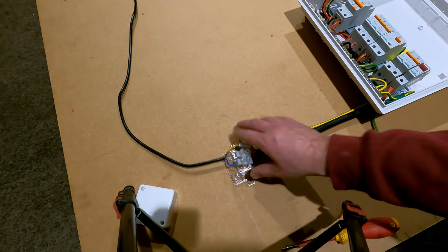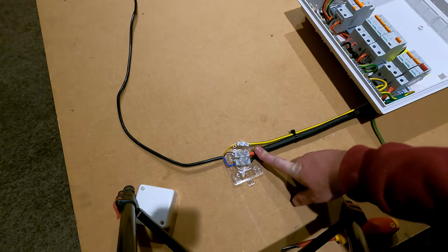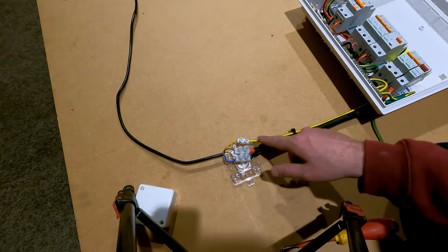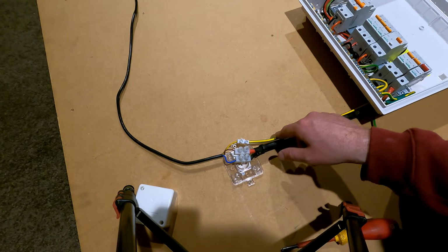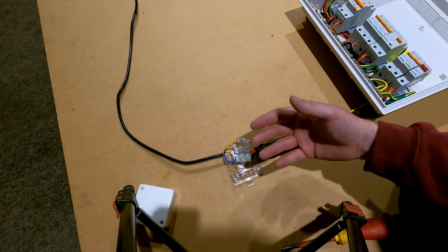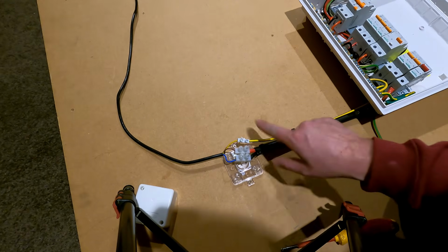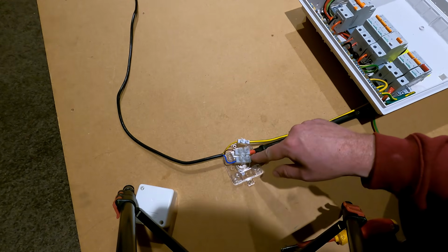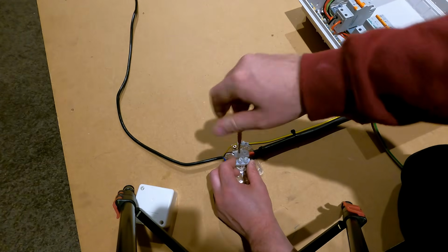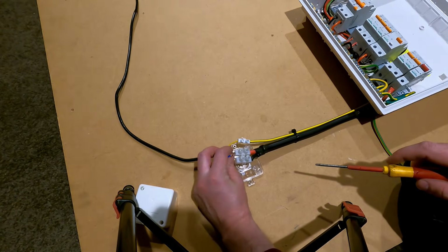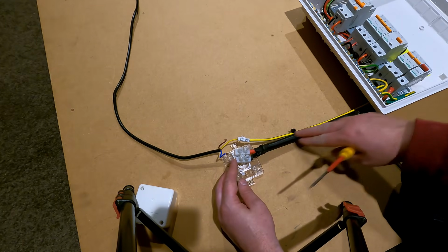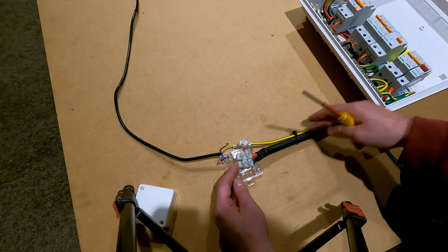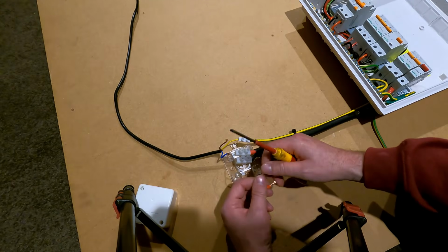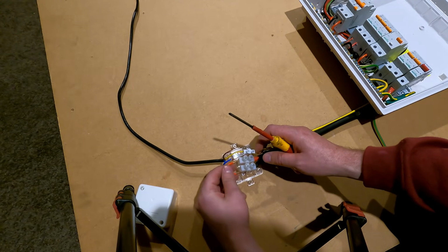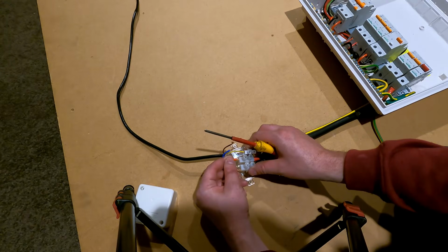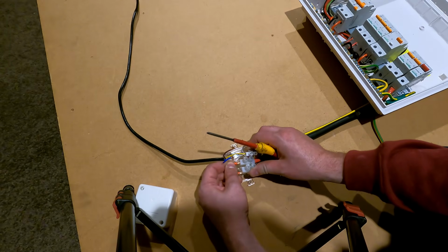This connection here would be in the meter box. Of course, this earth here is going to be our actual earthing conductor, our main earthing conductor. The other one that we've tested for the installation is just a dummy. But what we want to do is put a dead short between neutral and phase. Now one thing I hadn't mentioned yet was the size of the conductors. Here we've got 16mm neutral screen with a 6mm copper conductor. There is table 5.1, which you need to go by if you're using different sized mains to ensure you've got the right sized earthing conductor.